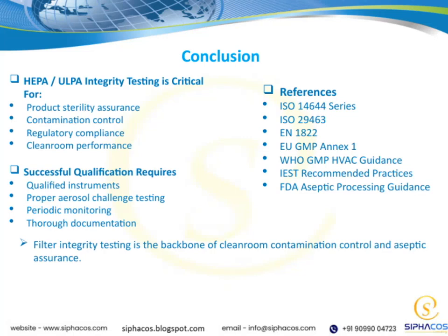Filter integrity testing really is the backbone of maintaining cleanroom contamination control and ensuring aseptic conditions. It's a critical step that supports many standards and guidelines, including the ISO 14644 series, ISO 29463, EN 1822, as well as regulatory references like EU GMP Annex 1, WHO GMP HVAC Guidance, IEST Recommended Practices, and FDA Aseptic Processing Guidance.